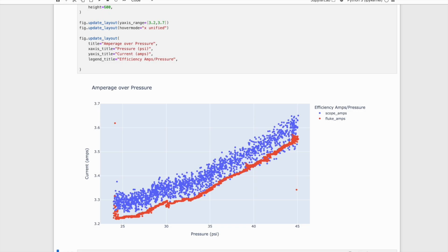So last night, when I first set this up, I did run one other capture of data. And when I graphed that data out, there was an interesting anomaly, like a jump discontinuity in this current versus pressure curve, where around the 44.5 psi mark, at those higher pressures, the motor was drawing more current. This is the kind of jump discontinuity in a curve like this that I think can be informative for looking at a system like this.